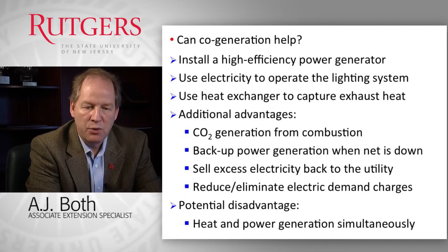In those cases where we do use cogeneration or combined heat and power, we could also try to capture the exhaust gases and clean them and use the CO2 in those exhaust gases as a supplemental source for the CO2 concentration inside the greenhouse. So in addition to generating electricity and heat for the greenhouse, we can also capture the CO2 in the exhaust gases and return them back to the greenhouse for improved plant growth and development.